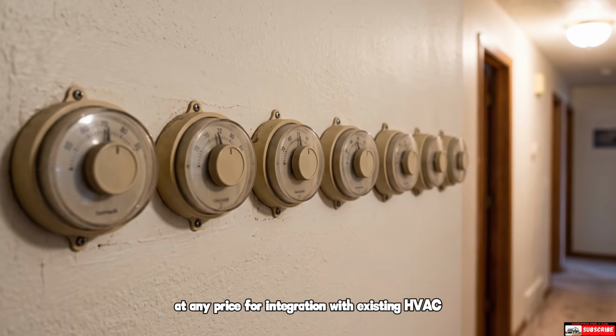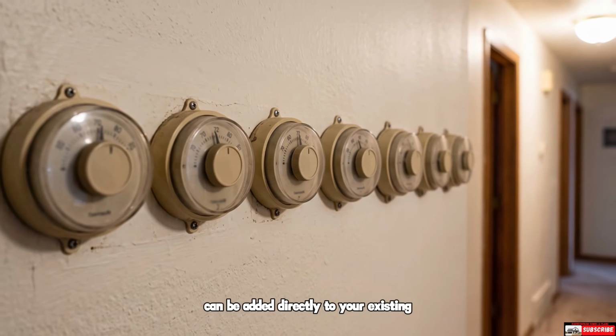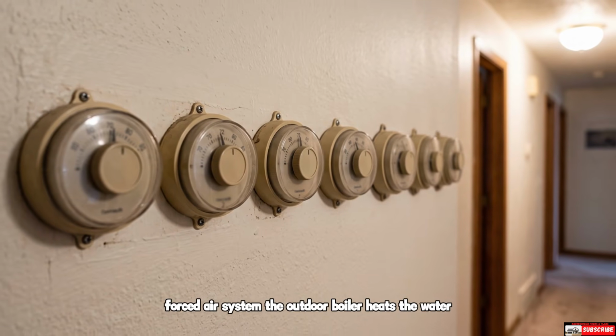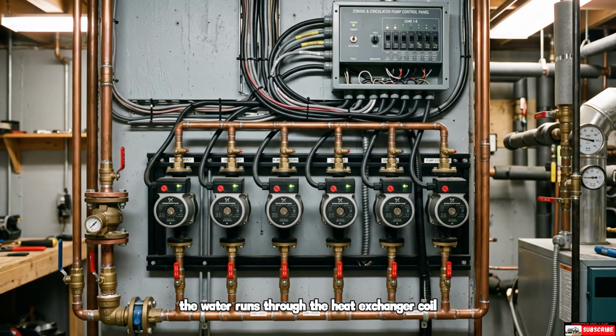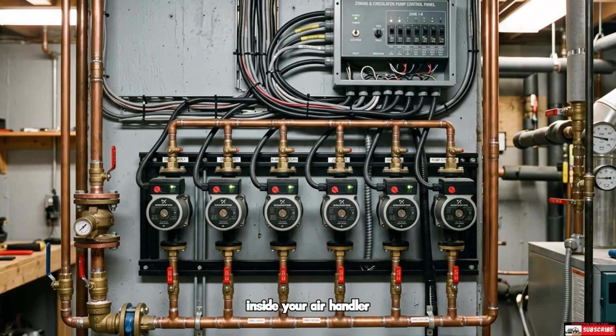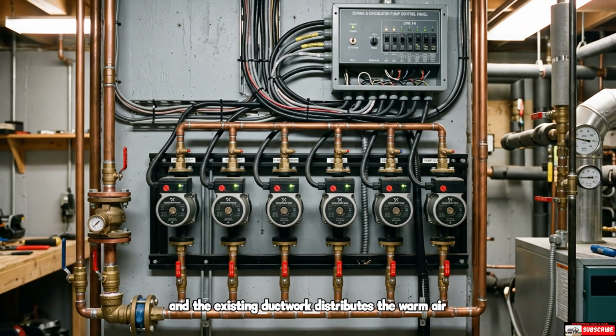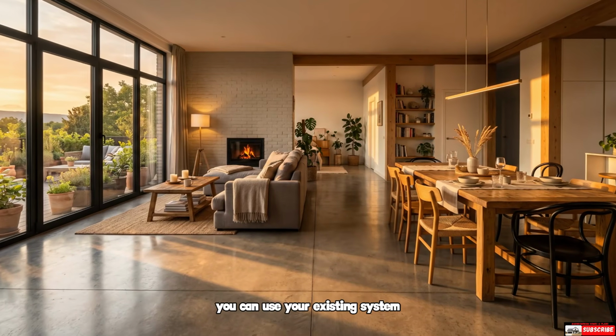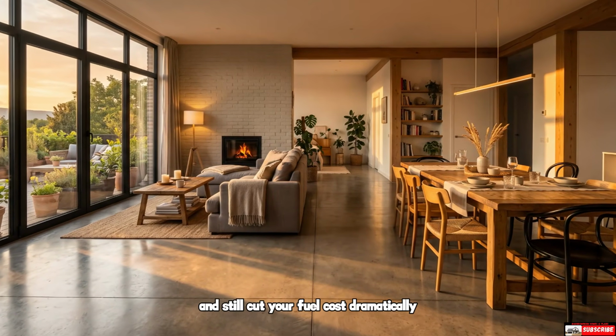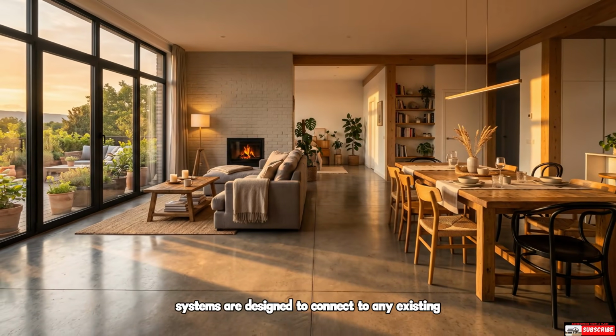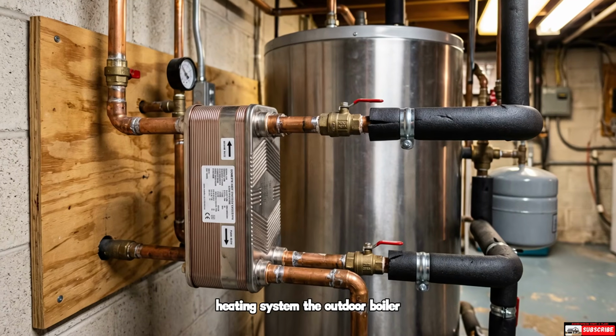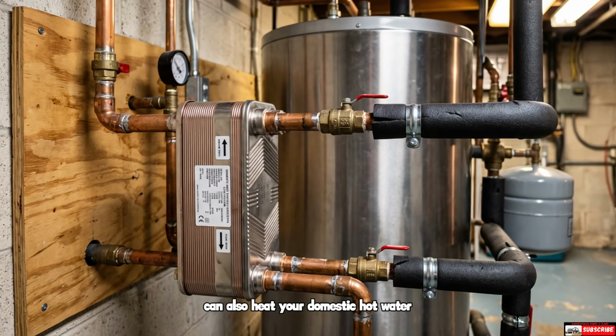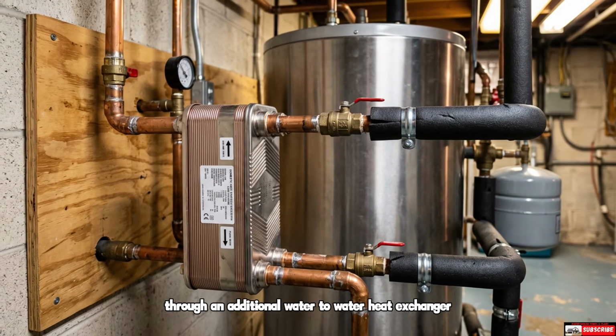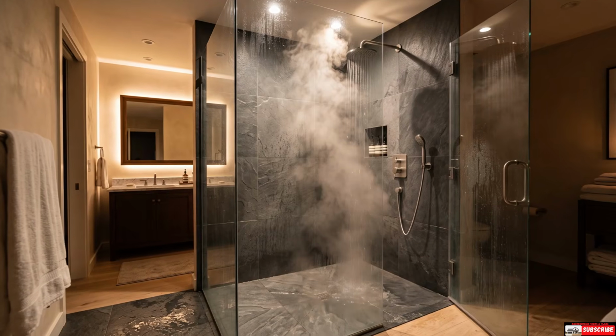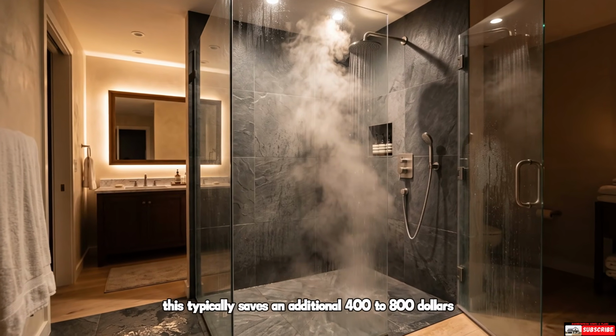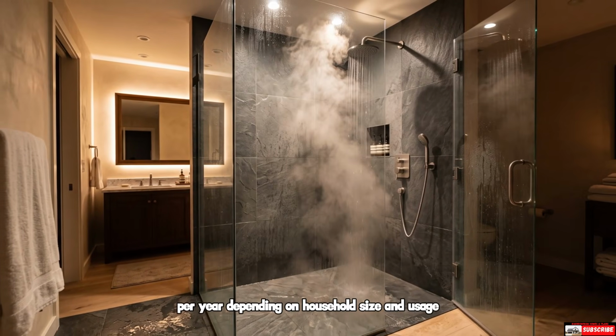For integration with existing HVAC, a water-to-air heat exchanger can be added directly to your existing forced air system. The outdoor boiler heats the water, which runs through the heat exchanger coil inside your air handler, and the existing ductwork distributes the warm air. You don't have to do radiant floors. You can use your existing system and still cut your fuel costs dramatically. Central boiler systems are designed to connect to any existing heating system. The outdoor boiler can also heat your domestic hot water through an additional water-to-water heat exchanger, eliminating your water heater entirely. This typically saves an additional $400 to $800 per year, depending on household size and usage.